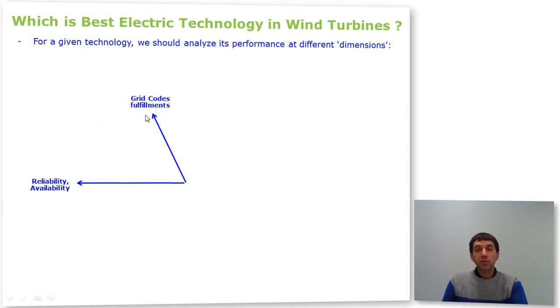Here in the past, the double fed induction generator was for some years the most effective and least costly solution, but now with the low voltage ride-through and high voltage ride-through requirements getting stronger and stronger, it has to be demonstrated whether in the future the double fed induction generator is going to be a good solution compared, for instance, with the full converter topology with a synchronous generator, for instance with permanent magnets. That's the debate, that's the main question.